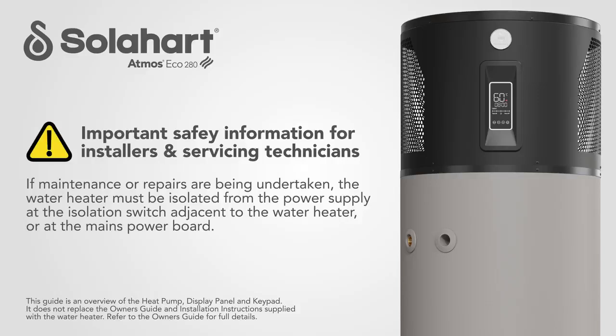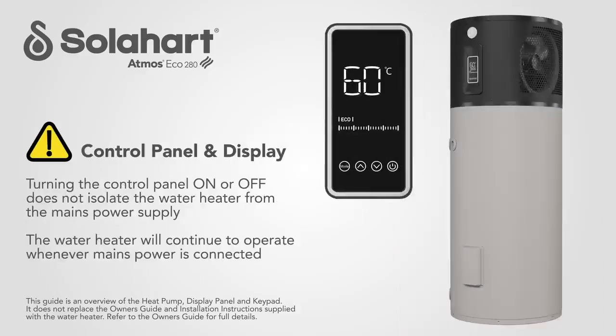If maintenance or repairs are being undertaken on the water heater, the servicing technician will need to isolate the water heater from the power supply at the isolation switch or at the mains power board. Note that turning the control panel on or off does not isolate the water heater from the mains power supply. The water heater will continue to operate whenever mains power is connected.